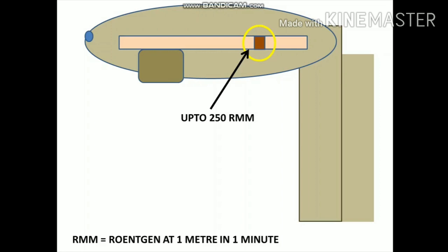This much higher activity source is also hazardous, so proper shielding is required for the safety of the patient, radiation workers and public. For this purpose, the source head is designed with a steel shell filled with lead or tungsten to make the equipment safer to use. The source remains in the off position when there is no treatment. For the treatment, the source moves to the beam on position, and you can see a rod coming from the source head. That means the radiation is on.